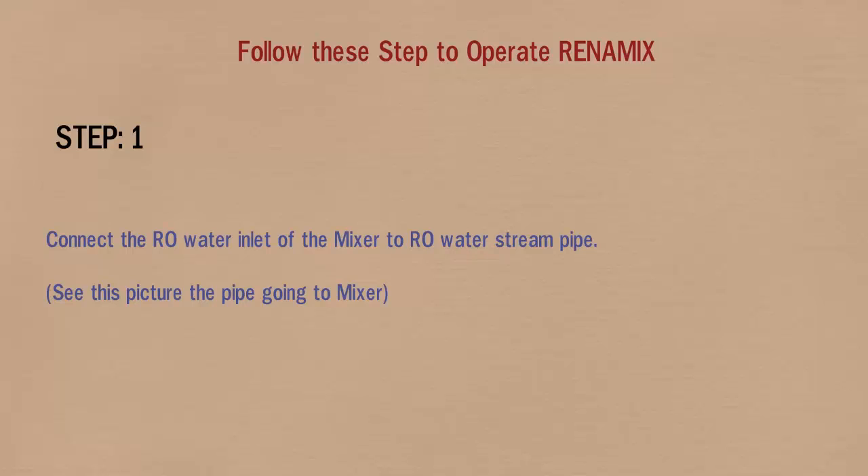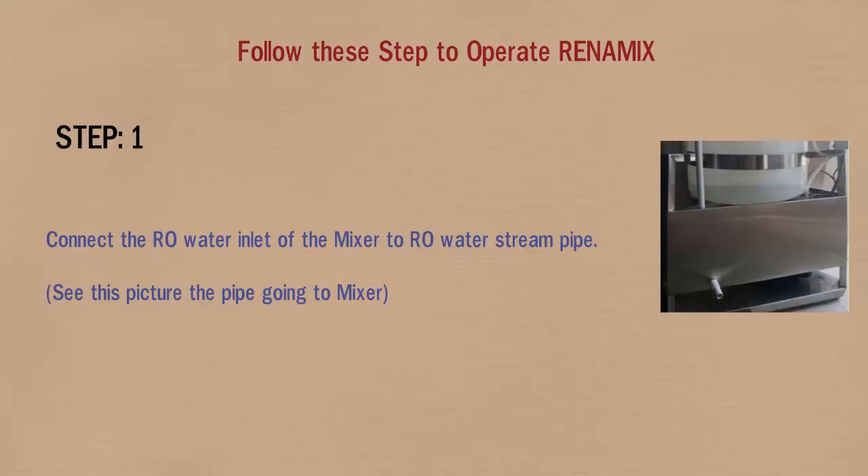Please follow these steps to operate RENAMIX. In step 1, connect the RO water inlet of the mixer to the RO water stream pipe. See this picture — the pipe going to the mixer.